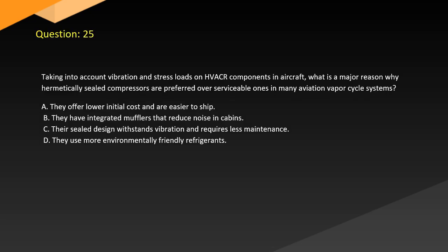Question 25. Taking into account vibration and stress loads on HVACR components in aircraft, what is a major reason why hermetically sealed compressors are preferred over serviceable ones in many aviation vapor cycle systems? A. They offer lower initial cost and are easier to ship. B. They have integrated mufflers that reduce noise in cabins. C. Their sealed design withstands vibration and requires less maintenance. D. They use more environmentally friendly refrigerants.